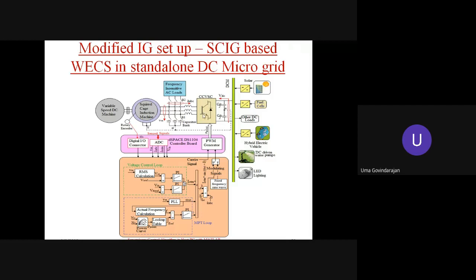Don't bother about the block diagram and all, it's very simple. The fundamental understanding is that the current controlled voltage source converter is a 4-quadrant converter. So it is possible to control this CCVSC. It's nothing but a 3-phase voltage source inverter. It is called current controlled voltage source converter because the control mechanism is on the current. It can be made to operate either as a pure inductor or as a pure capacitor, or for whatever the power factor or whatever the VAR support, it can be made to supply either the lagging VAR or the leading VAR by proper control.